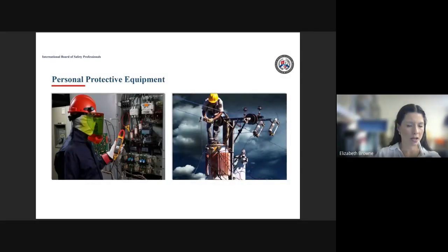Here's an example of some other levels of personal protective equipment where we've got the hard hat and a face shield. This individual is also wearing a balaclava for face protection that would be arc rated or flame retardant. And then his clothing would also be arc rated. For the highest level of protection, they have a fully enclosed suit that we may need to require employees to wear if they're working in a really high voltage environment.